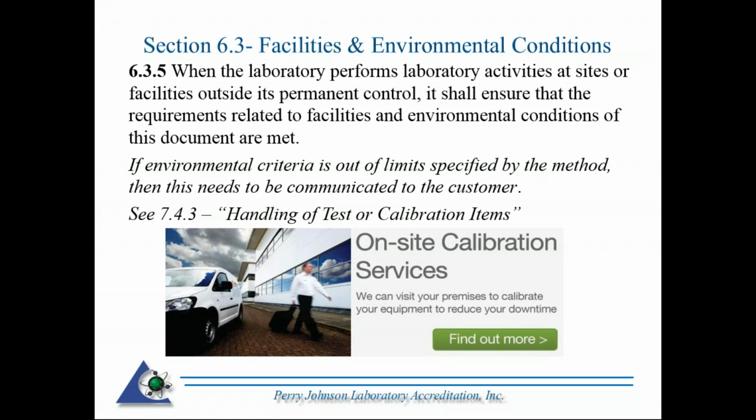Hence, according to 7.4.3, what would need to be done in that instance is the laboratory shall consult the customer for further instructions. The customer needs to be informed that the environmental conditions at the customer's location are outside the specifications to perform the test or calibration, and this consultation needs to be recorded.